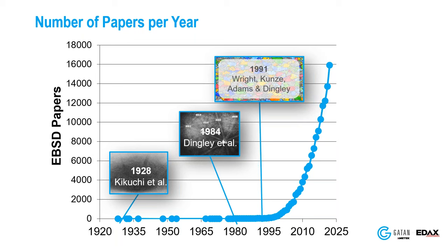Question: What is the minimum acceleration voltage required to get good EBSD data? It's difficult to do mapping for anything really less than 5 kV, and even 10 kV can be quite challenging. We typically operate at 20 kV unless we have a special condition. We typically don't do really low kV work unless we're using a direct electron detector, because the phosphor detector is not sensitive enough for those low kVs to capture the weak signal in those patterns.